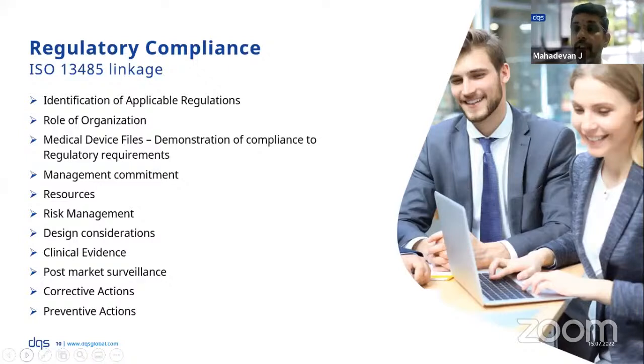The next important thing which the ISO standard also specifies is the medical device file. There is a separate clause in the standard for the medical device file, which states the minimum requirements. I say minimum requirements because, with the type and complexity of the device and with respect to the operations of the organization, the contents of the medical device file vary. Based on the product and the regulatory requirements which the manufacturer needs to comply with, the contents keep varying. It may be lesser, it may be more.